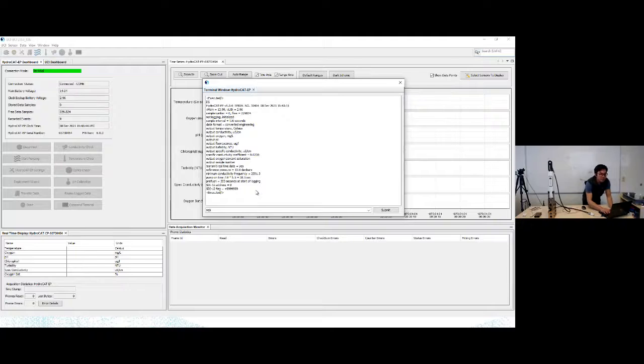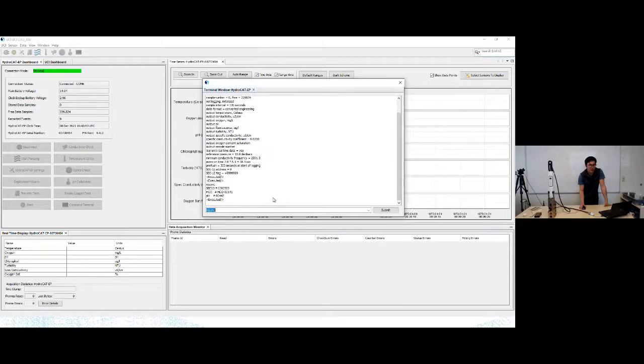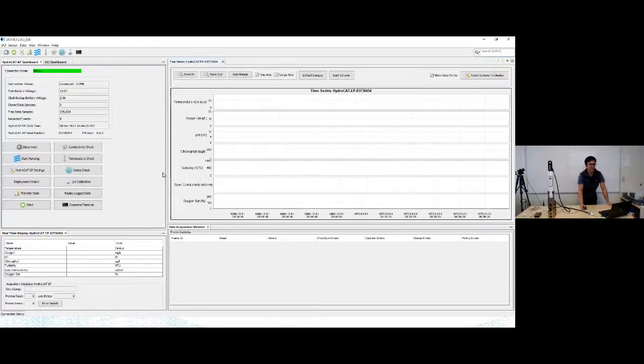And because I installed a pH sensor, I'm just going to try this, make sure everything's cool. You can send the resync command, and that's going to make sure that your HydroCAT is properly talking to all of the sensors installed on it. That is the SBE63, the ECO optical sensor, chlorophyll and turbidity, and your pH sensor. When I install a new pH sensor or replace the pH sensor, I like to send this resync command to ensure that my HydroCAT sees and is listening to all the sensors on my instrument, including this pH sensor that I recently installed. Okay, so command terminal, all good to go.